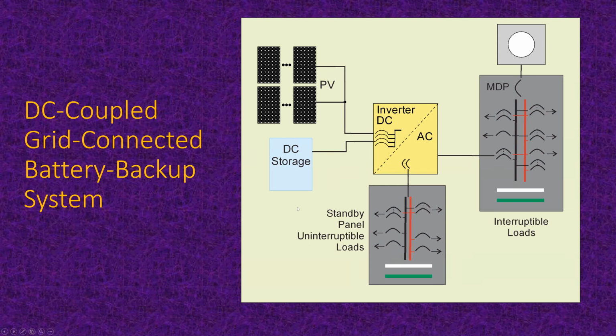And then you do the same math if you're really curious about what this thing will do for you, depending on the size of the PV, the size of the storage, and the kind of loads you've got. Now, one thing that's happening now is people are forgetting to do that. And sometimes they're putting way too little storage and way too much PV to have an efficiently operating system. So you've got to be careful. That's why I wanted everybody to see those rules at the beginning, because it's really easy to mess up these systems if you don't pay attention to what the manufacturer says. Now, the inverter manufacturer is going to tell you that the DC storage has a rated output power.